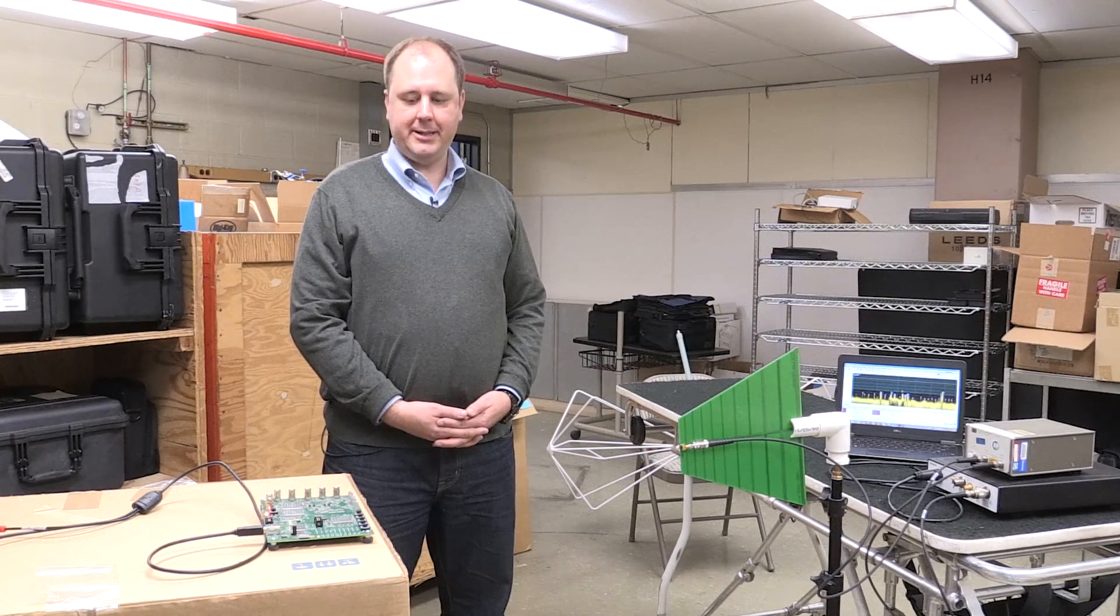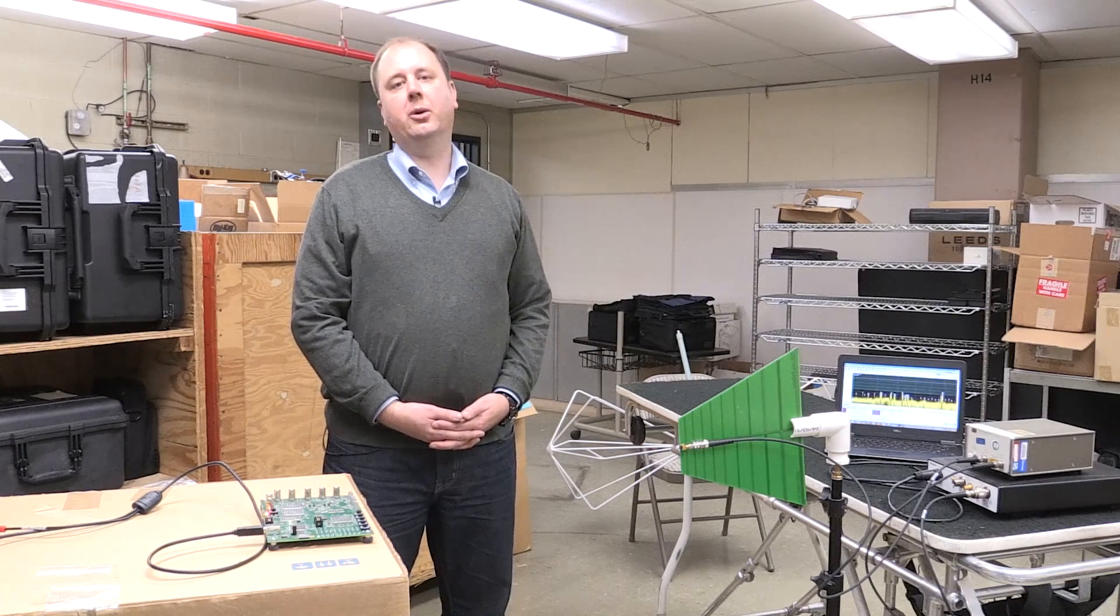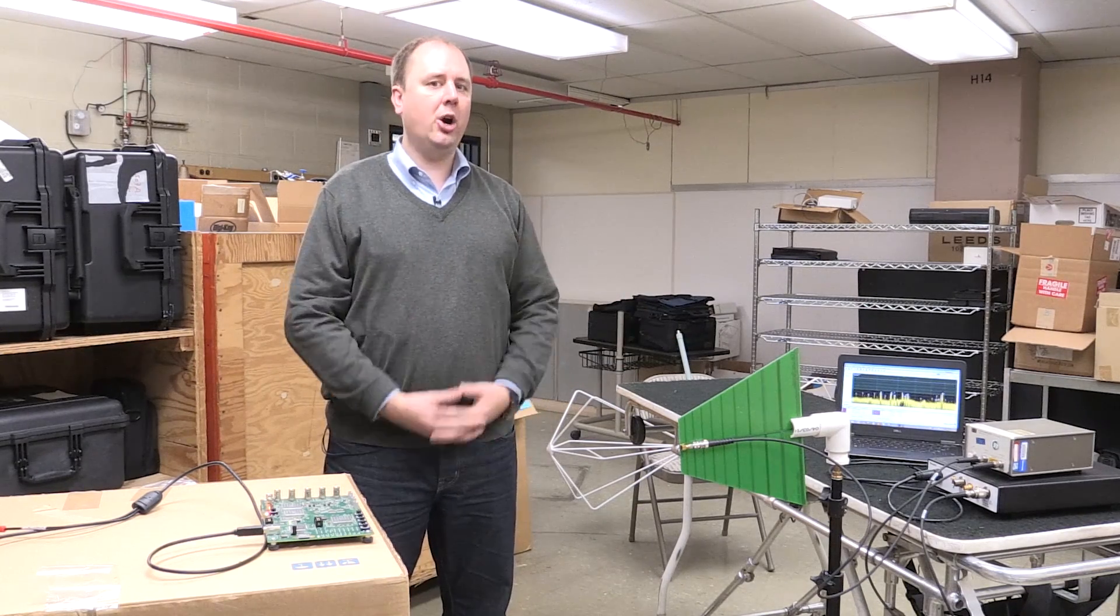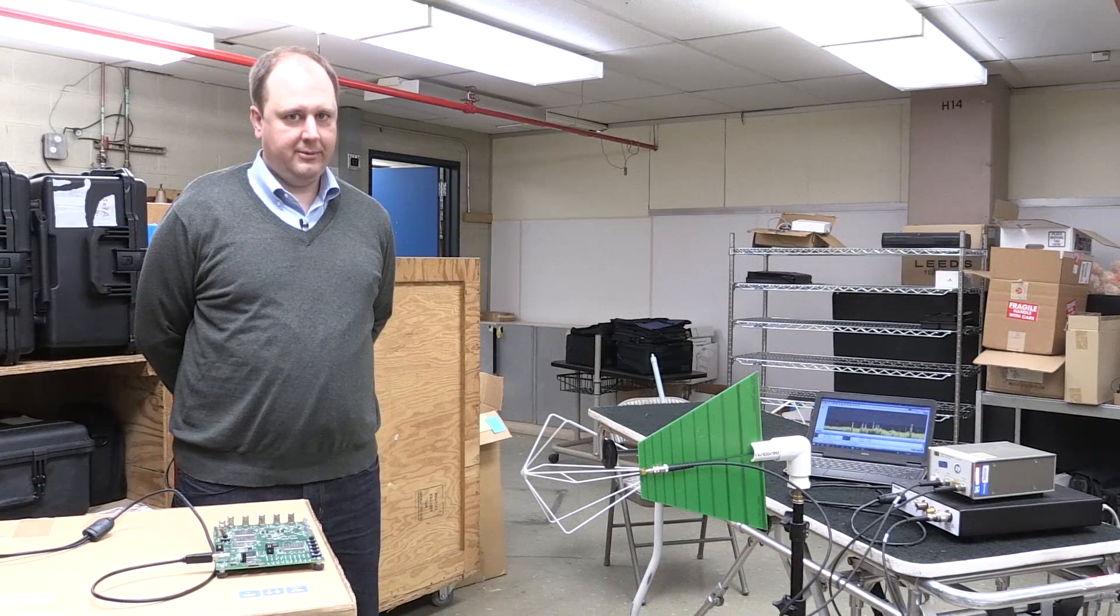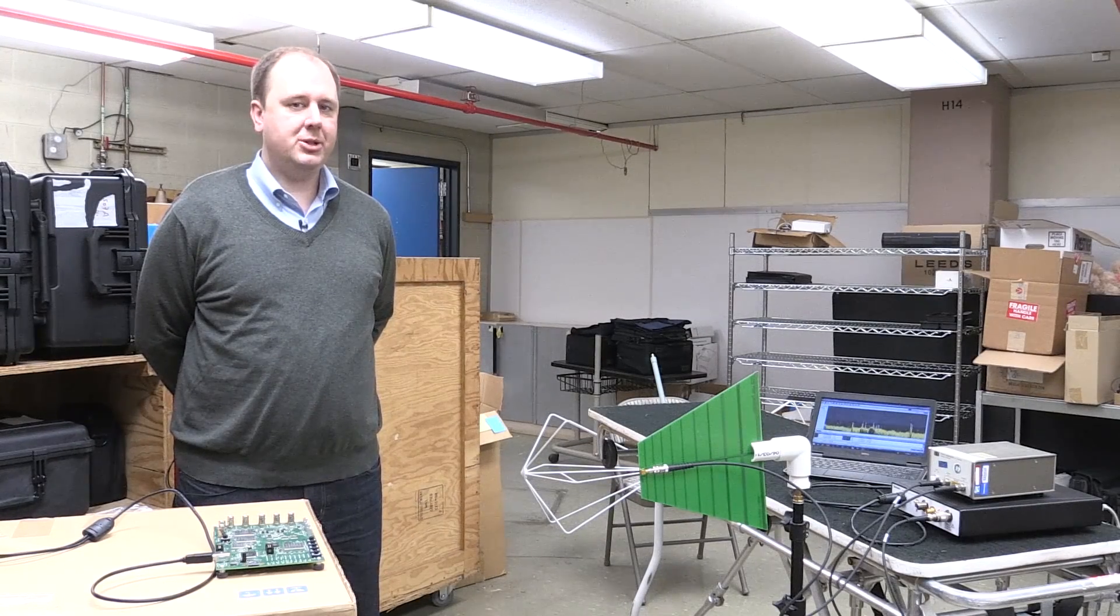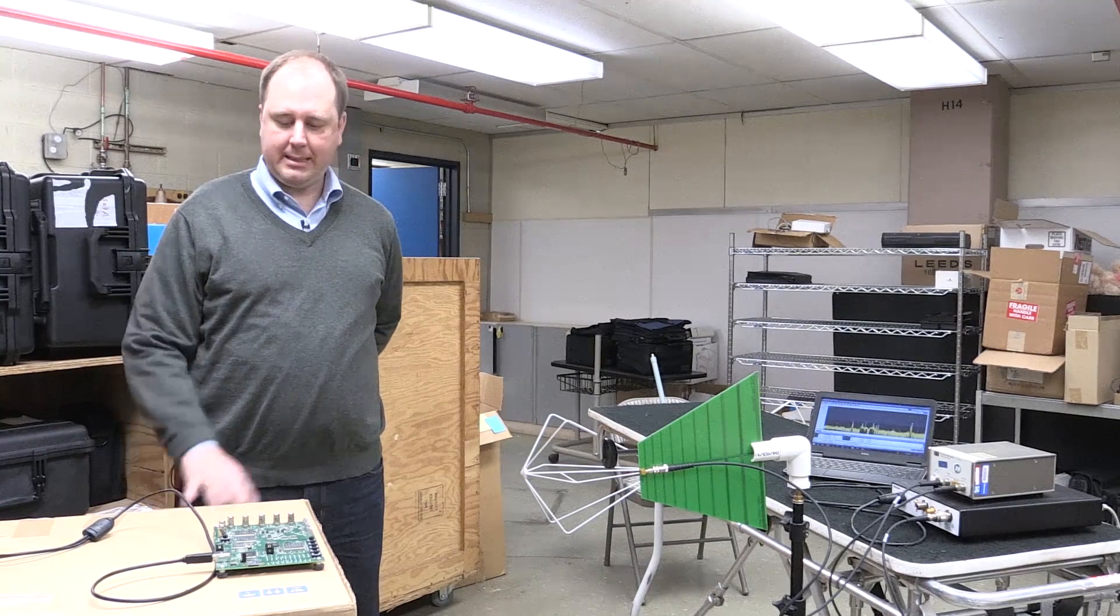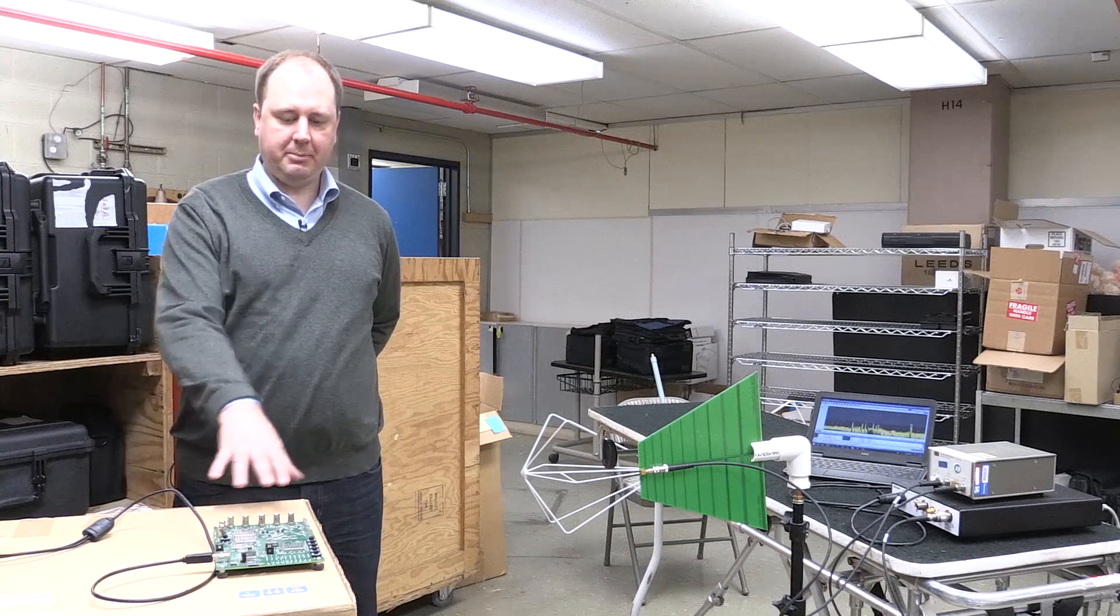So here we finally have our device under test set up. It's interesting to note we're in the basement of a large building here and we actually had to go into multiple rooms trying to find the quietest RF environment that we could use. So now we'll look at the low-cost way of doing EMI pre-compliance sweeps.